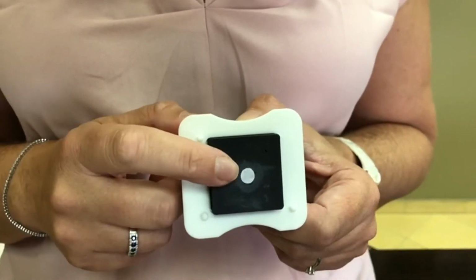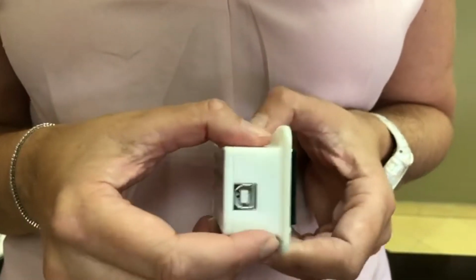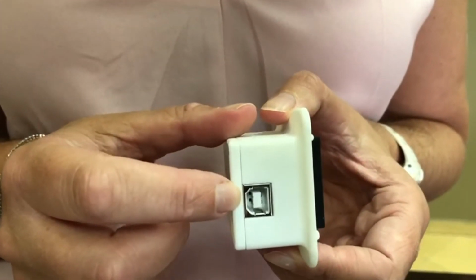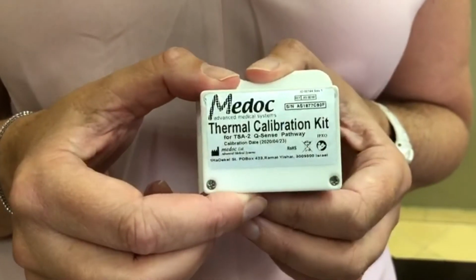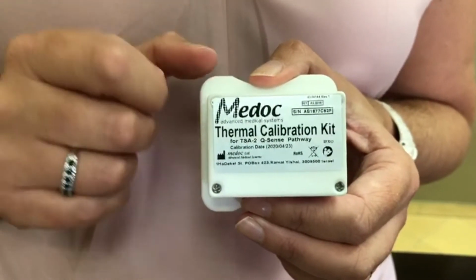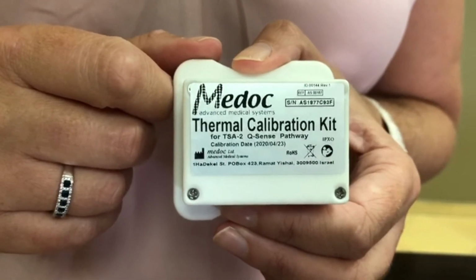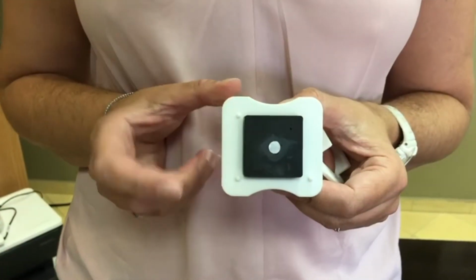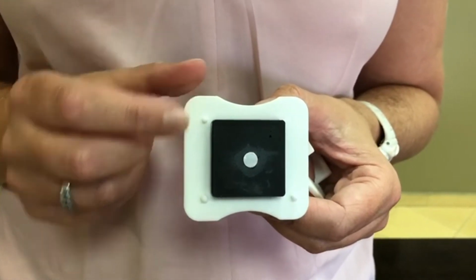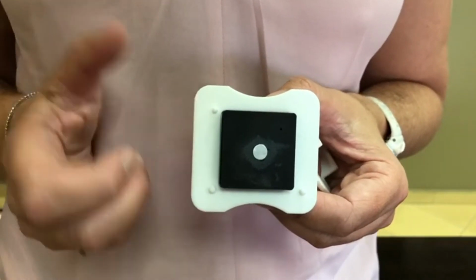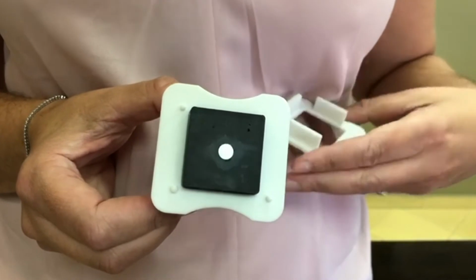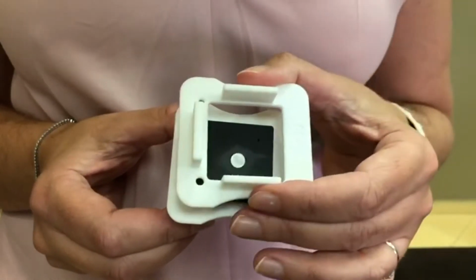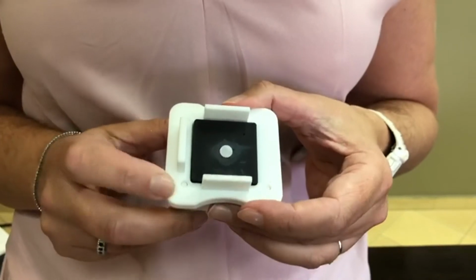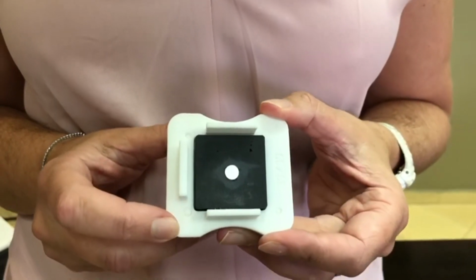This is the sensor that will sense the temperature. Over here, we'll connect the communication cable to the computer. And over here is the data, the serial number, and also the calibration date of the sensor. Now we're going to set up the calibration kit and put it all together. Okay, so here we got our sensor, and you can notice that there are 3 pins over here, and these pins are actually there to hold the jig. Let's connect the jig for a second. And you can see that these pins align with 3 holes in the jig.